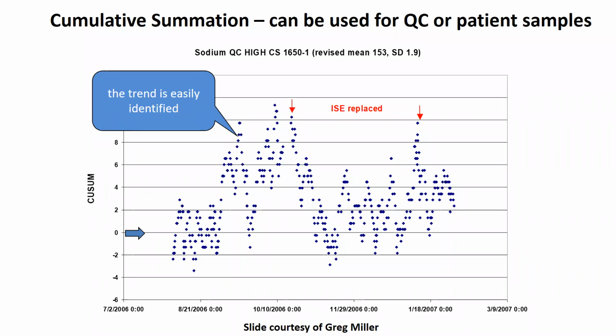The advantage to this technique is a more sensitive or earlier detection of errors compared to the most widely used QC multi-rules, especially when routine assay standard deviations are large, like in a poorly performing assay. The disadvantage is that simulations and modeling are needed to optimize the alert values, so technical expertise is required. However, automated tools for optimization and implementation are becoming available from the manufacturers.